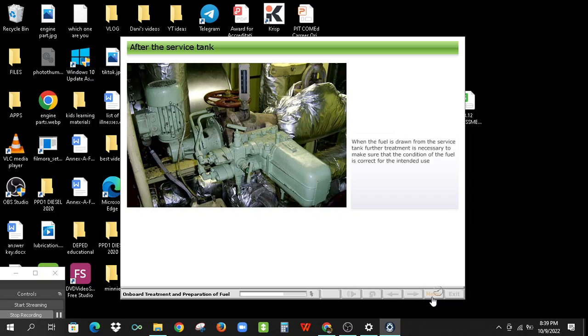When the fuel is drawn from the service tank, further treatment is necessary to make sure that the condition of the fuel is correct for the intended use. Fuel for a diesel engine, for example, has to be heated to ensure that the viscosity is correct for injection. We saw in the previous section that inline blending and fuel emulsification are also used, normally after the service tank. This further treatment is part of the in-use system and is covered in the module on fuel systems, Seagull CBT number 9.